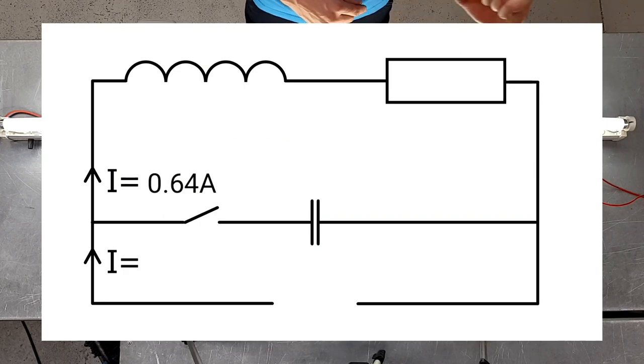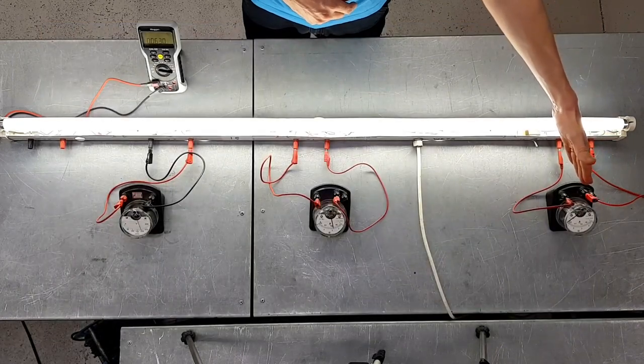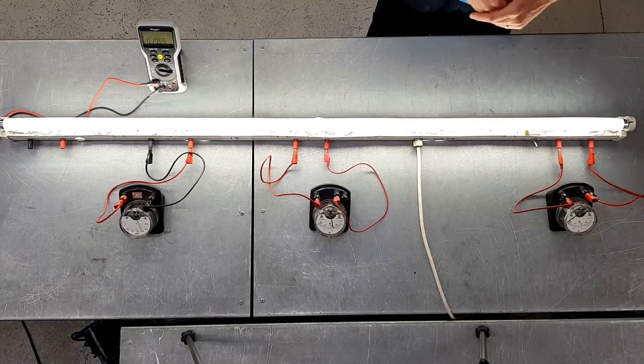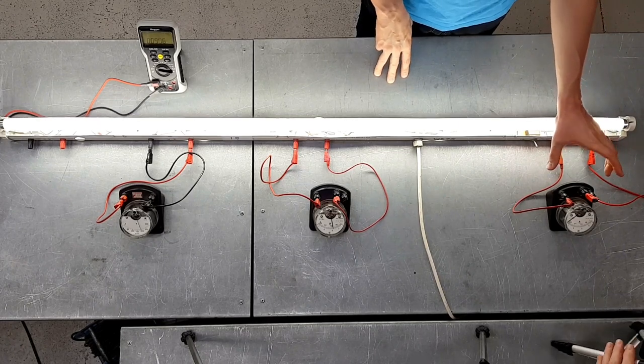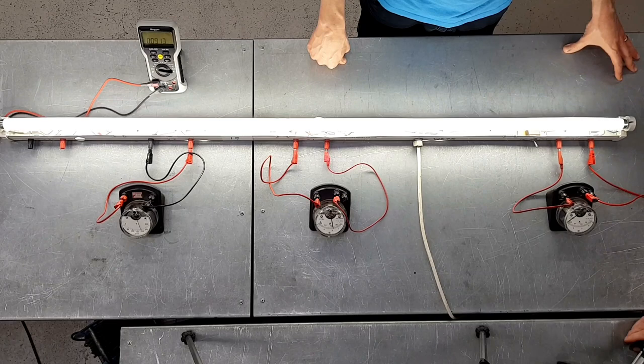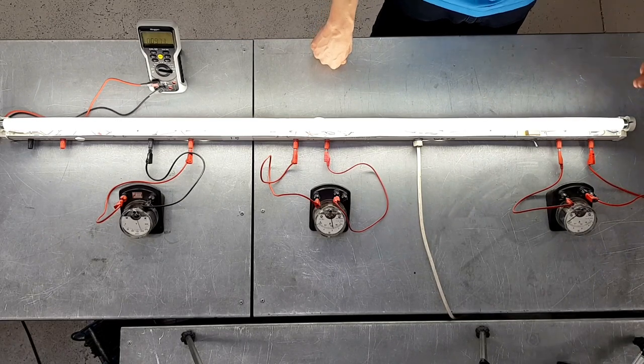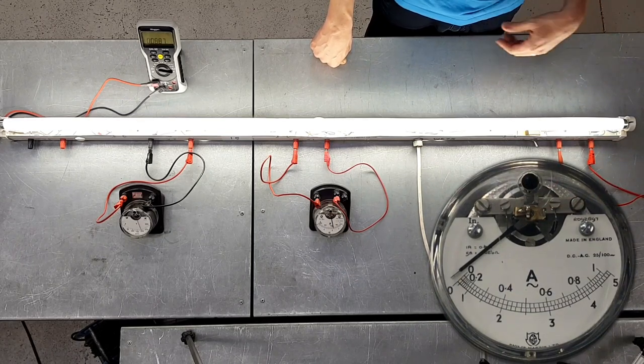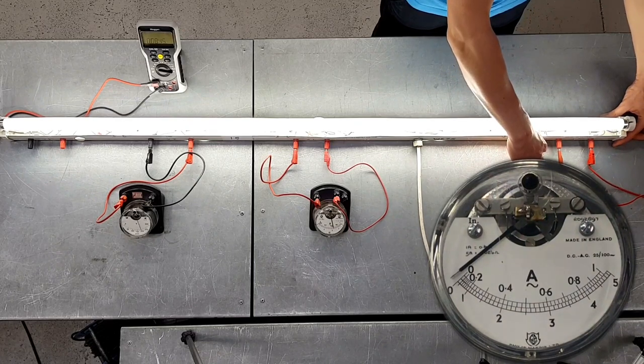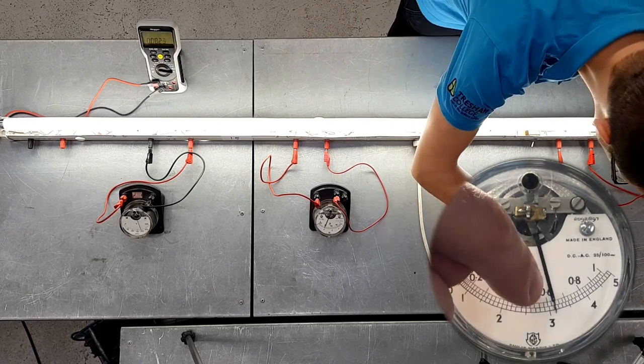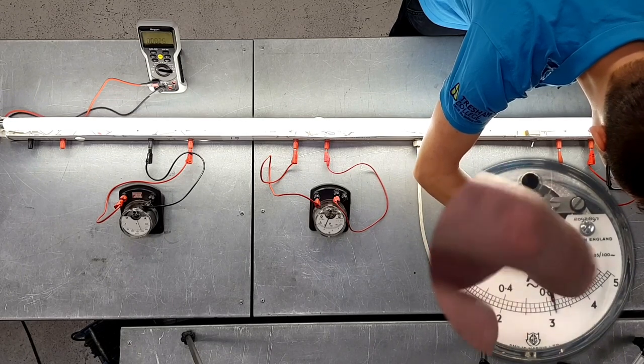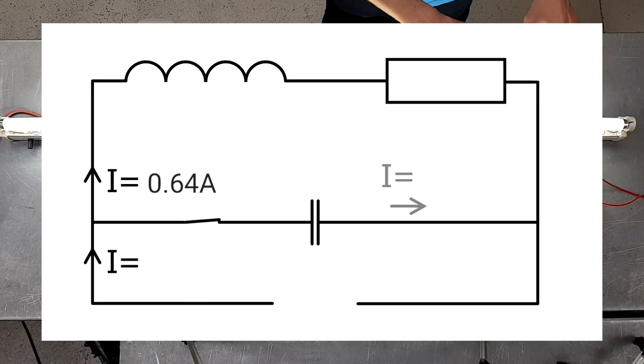Okay, what we're going to do now is go over to our power factor correction capacitor and introduce that into the circuit. This ammeter is going to tell us how much current is flowing into the power factor correction capacitor. At the minute it's disconnected so there is absolutely no current flowing through there, so we'll switch the power factor correction capacitor on. We're getting just over 0.6 - about 0.63 amps flowing into the capacitor.